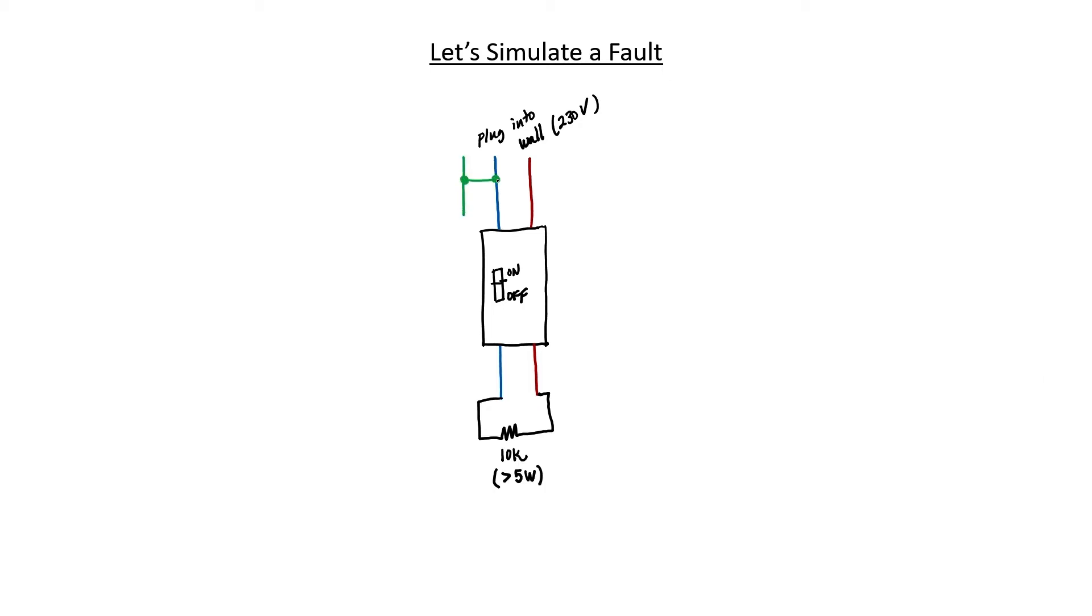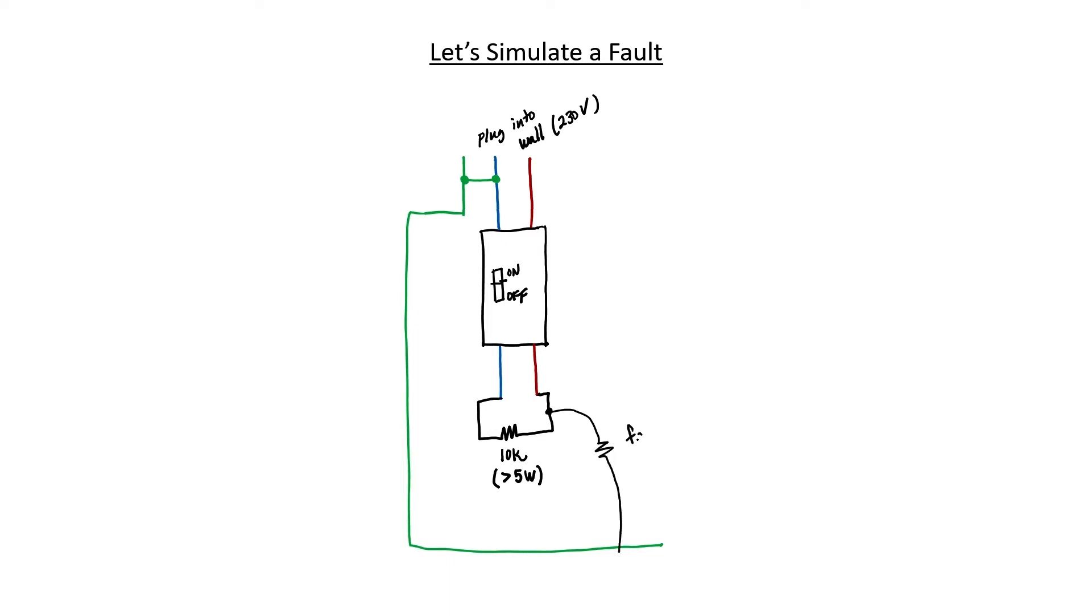We won't be using the third prong of the plug in this particular simulation of a fault condition, but we know that somewhere back in the electrical circuitry of the building, the neutral is tied to the ground. To simulate a fault condition, I'm going to hook a second resistor from the hot side after the switch to ground or to neutral. Without that resistor in place, the current coming out through the hot side and going back through the neutral side would be equal. However, with that fault resistor in place, some of the current that flows out through the hot side through the switch will not be flowing back through the neutral. If we use a large resistor, then that fault current will be very low and the circuit breaker won't trip. But if I use a lower value for the fault resistor, then we should be able to make this circuit breaker trip. Let's go over to the bench now and try out this little experiment and see if we can get this ground fault circuit breaker to trip.